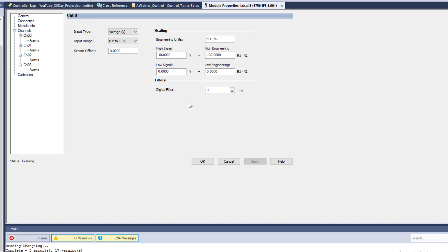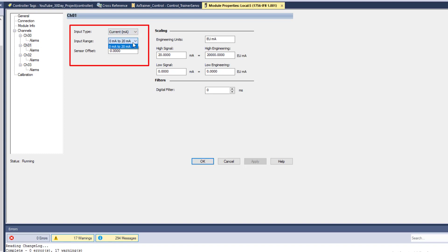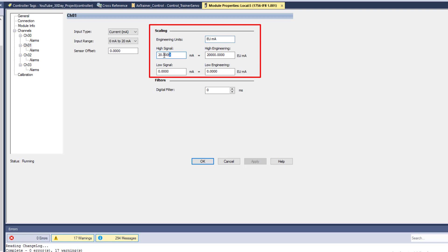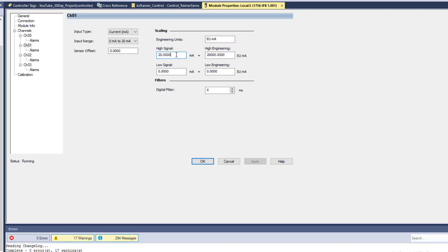Now let's talk about milliamps. I can set the card to current. Your card may be able to set to zero to 20 milliamps, or also four to 20 milliamps — generally speaking the industry uses four to 20. In this card I can only scale between zero to 20 milliamps. So my high point, which is 20 milliamps, I'm going to put in 20,000. I could use that as a percentage if I wanted, like 100%, but in this case I'm showing zero to 20,000, and zero milliamps would be zero.